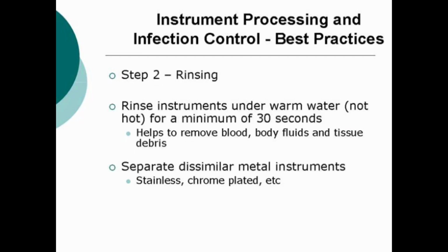Step 2, rinsing. Rinse the instruments under warm water, not hot, for a minimum of 30 seconds. This will help remove blood, bodily fluids, and tissue debris. You want to separate, as discussed earlier, dissimilar metals, including stainless steel, chrome-plated, and carbides.